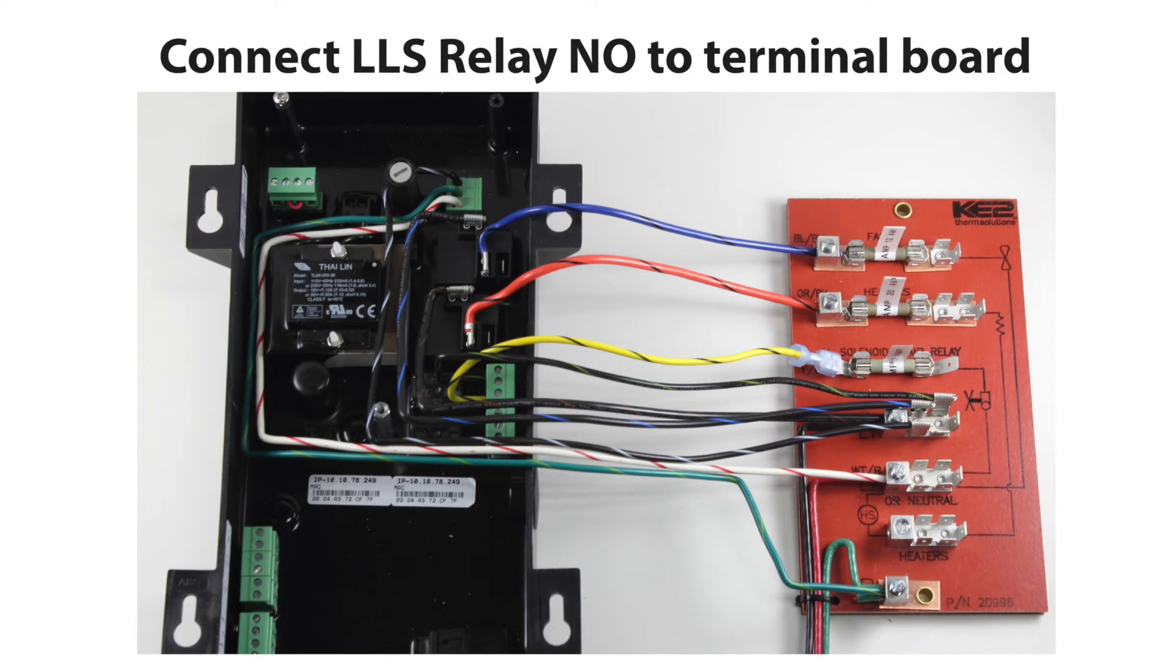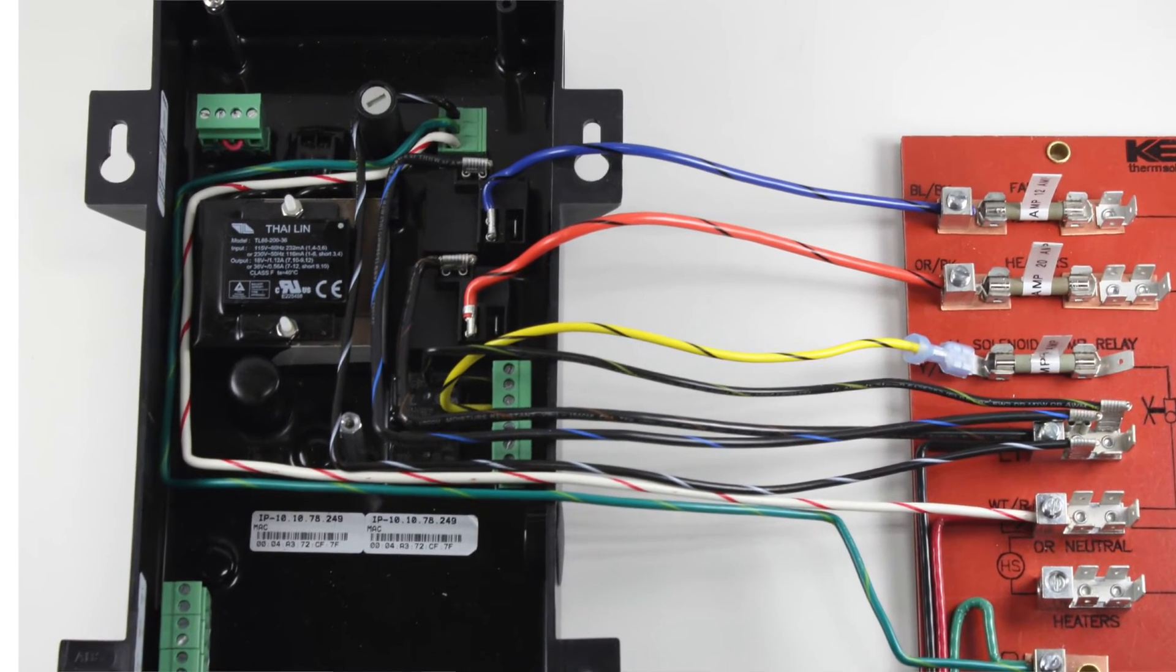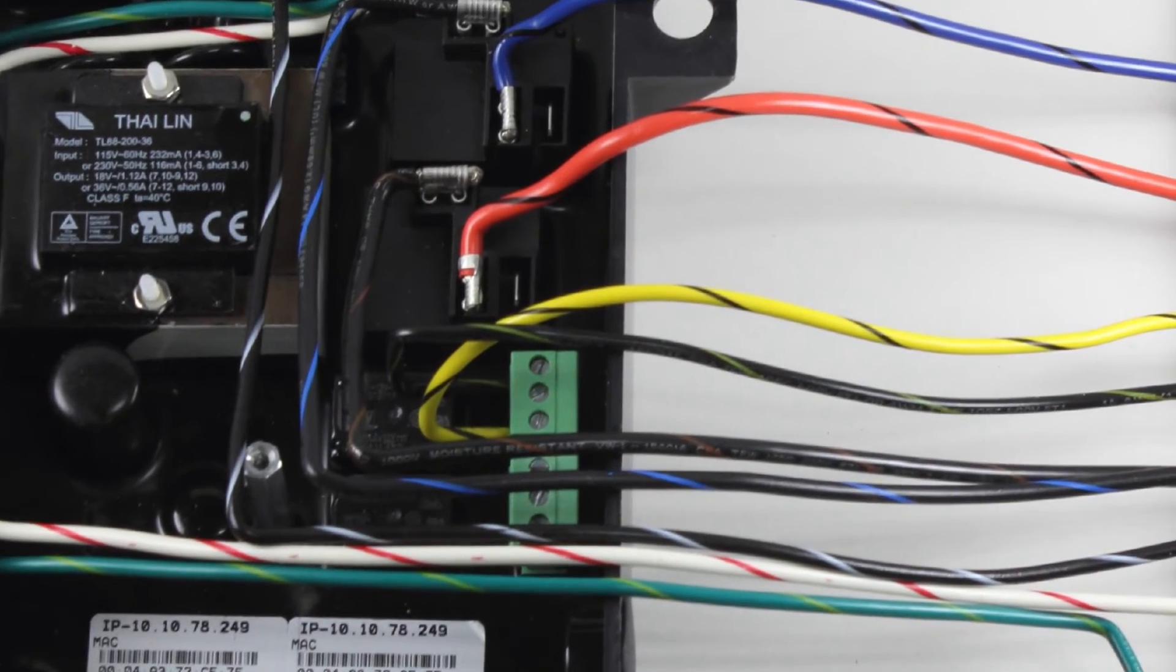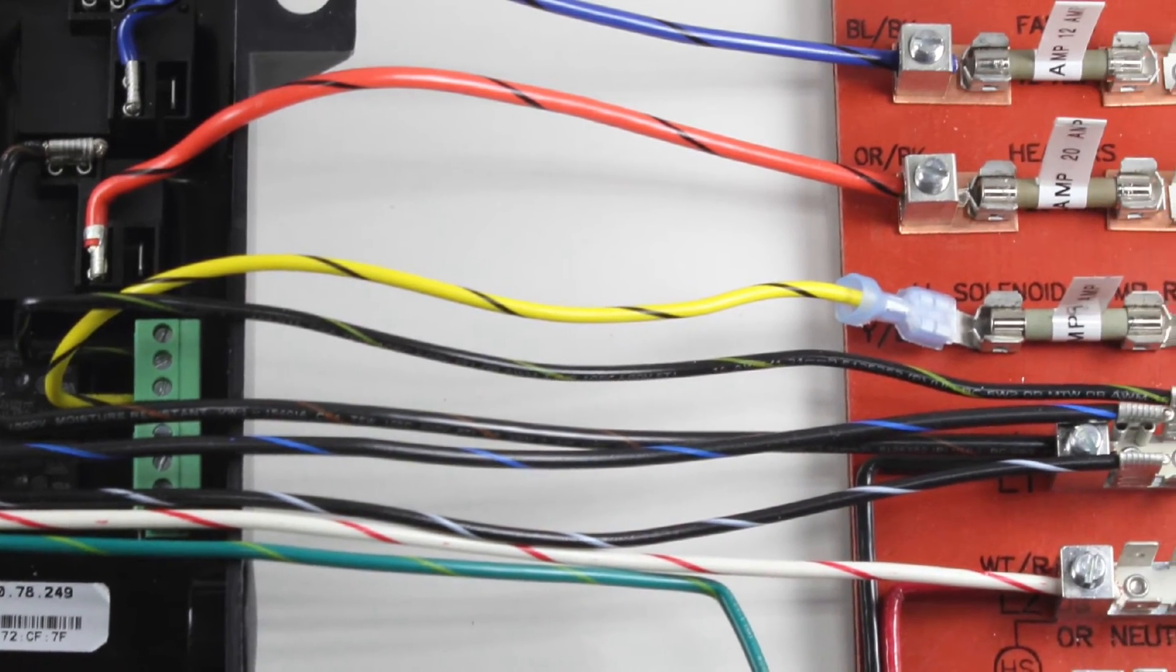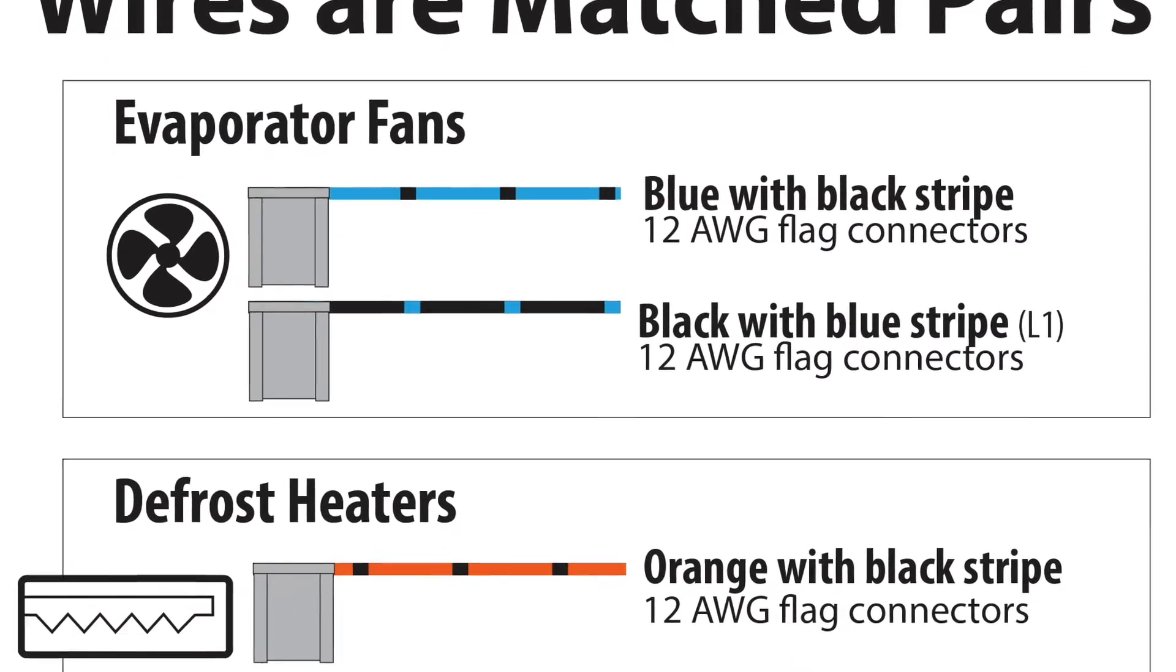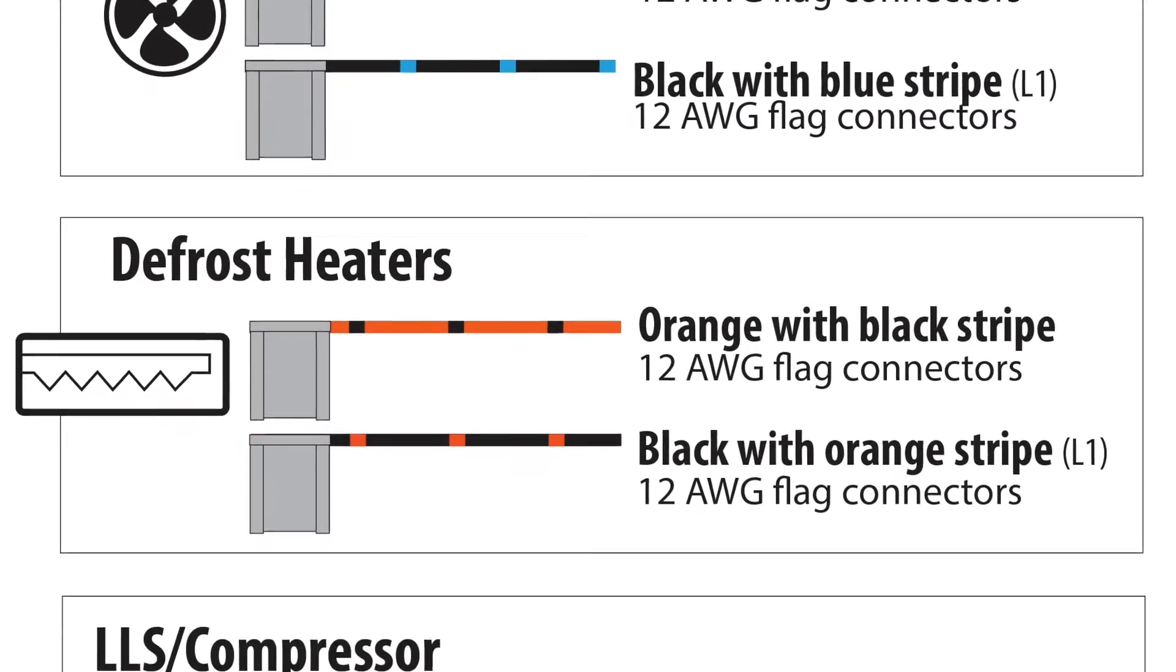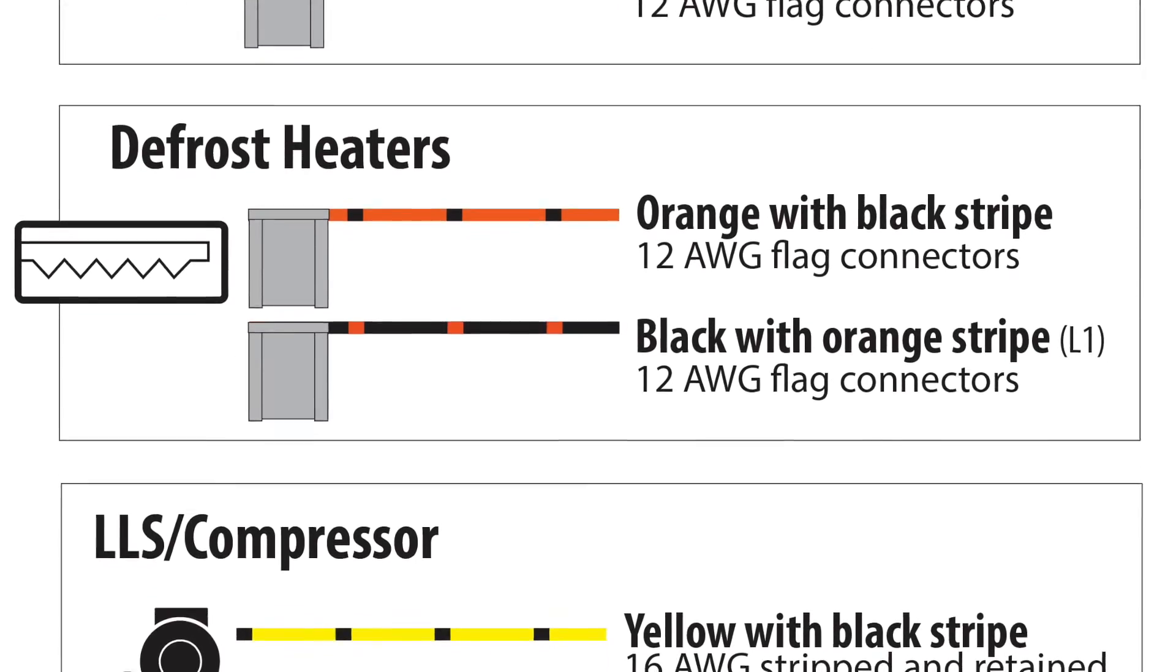Connect from the liquid line solenoid relay normally open set of contacts using the yellow with black stripe wire. Wire to the yellow with black location on the terminal board. You should notice the wires are color coordinated as matched pairs to keep the installation and service very simple.